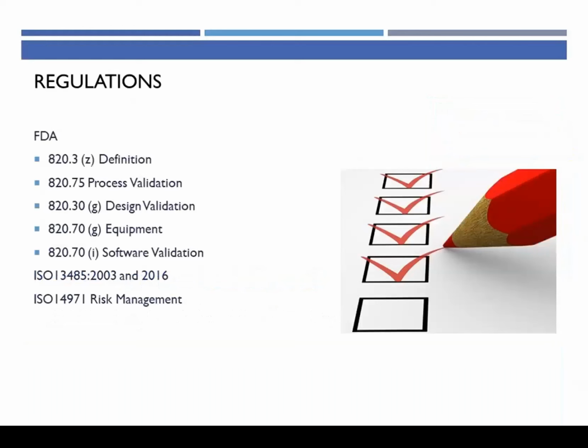So the first thing we want to do is look to the FDA regulations. If you're selling product in the US, you need to understand the quality systems regulation found in 21 CFR Part 820. In particular, we'll look at 820.3, paragraph Z, which contains some applicable definitions. We'll go through 820.75, which talks about the requirements for process validation. We'll touch on 820.30 paragraph G, which covers design validation. Now, this is not a course on design controls today, but we do need to know that there is a linkage between design validation and process validation.